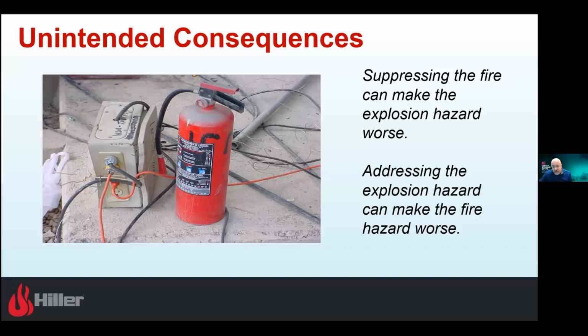So we're effectively moving it from a fire condition to an explosion condition. And guess what happens if we decide to vent or address the explosion? Well, we start moving air through the container, and the fire picks back up. So I've got some thoughts on that I'll express in a few minutes, but ideally the code is written now to give us a better handle on the mitigation measures for explosion.